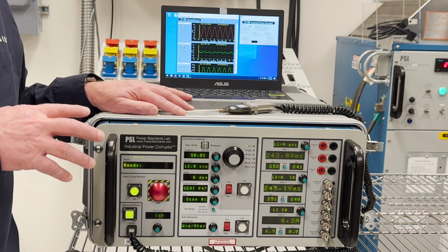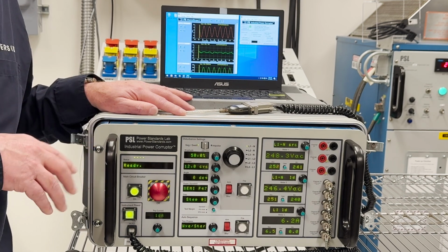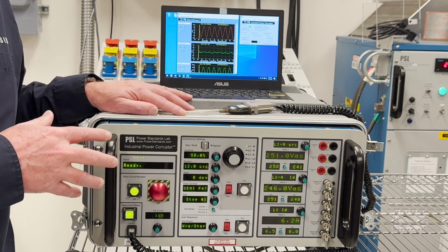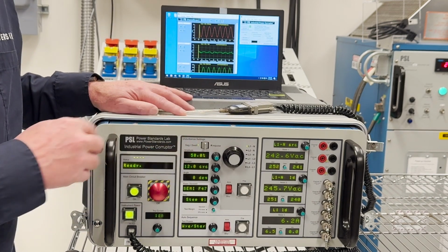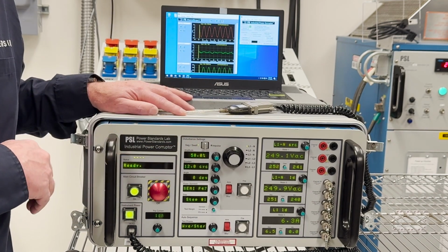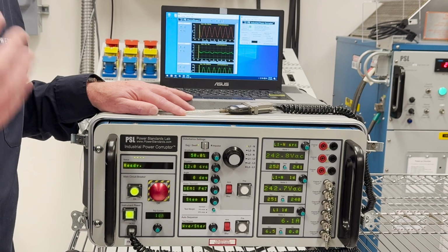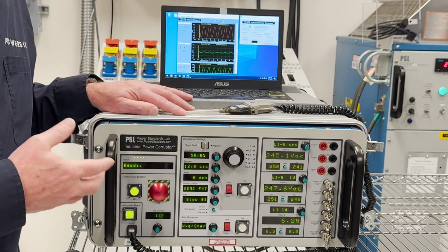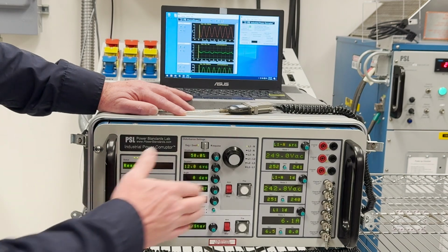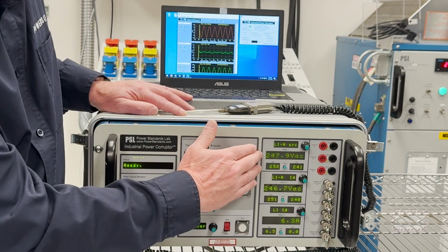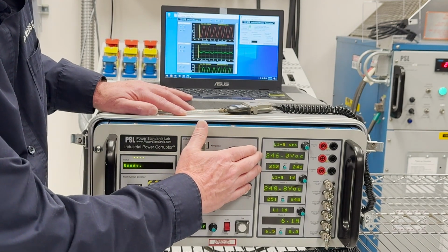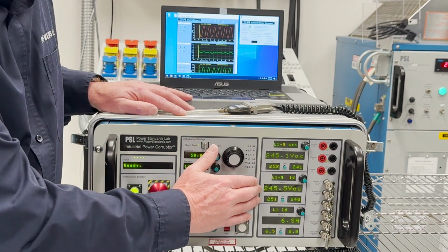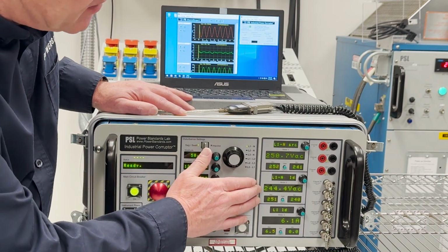So before we go and fire our first disturbance and start the process of testing, let's see where we are in terms of the gauges. Let's see the settings on the IPC, and let's see what we would recommend you do as a beginning to the test process. So here we can confirm we still have our line to neutral on the source side. We have line to neutral on the load side, which is as we would expect.